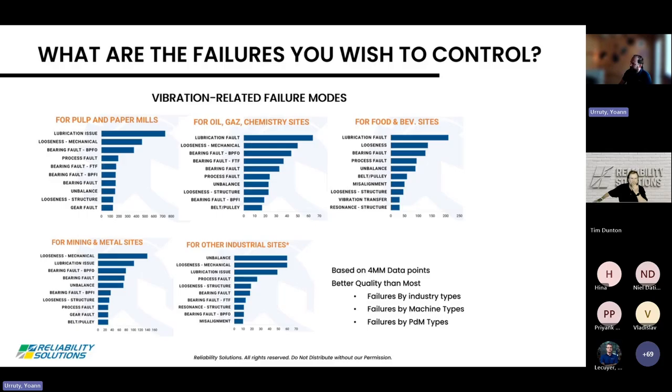I think we spanned over a couple of years in a certain area of North America where the standards are the same. So we extracted, I think, 300,000 vibration measurements or collections. And out of that, we extracted, I think, a few thousand alerts, right? So in the end, the ratio of normal results versus alerts was around 4 to 5%.